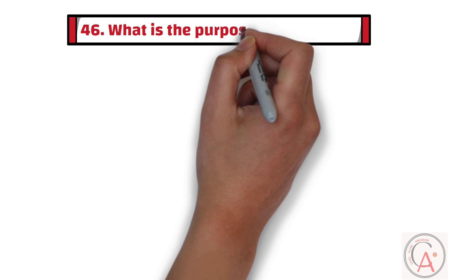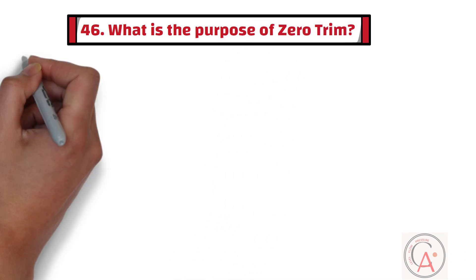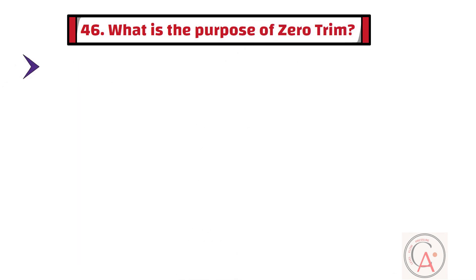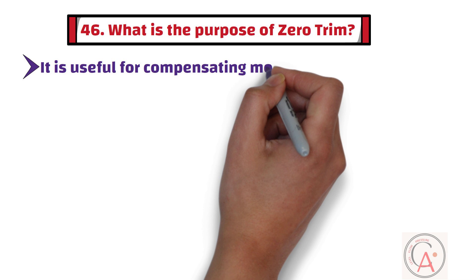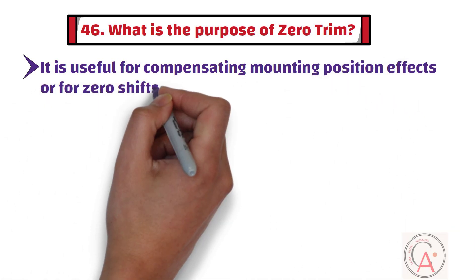Question 46: What is the purpose of zero trim? Zero trim is useful for compensating mounting position effects or for zero shifts due to static pressure in DP applications.